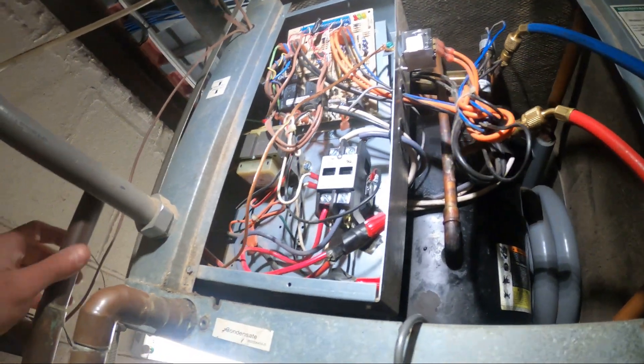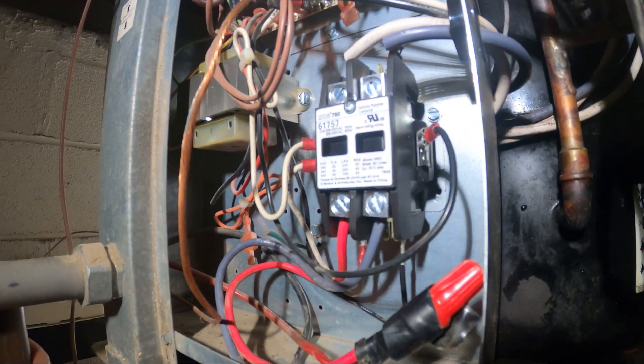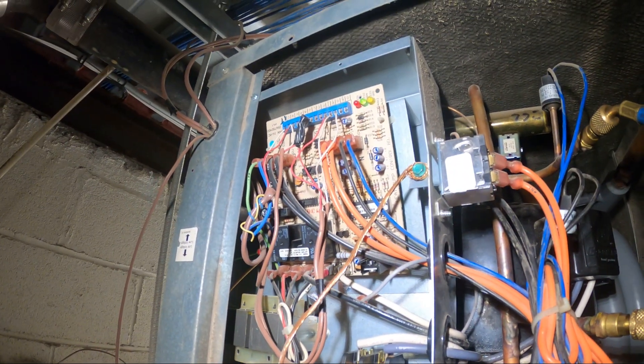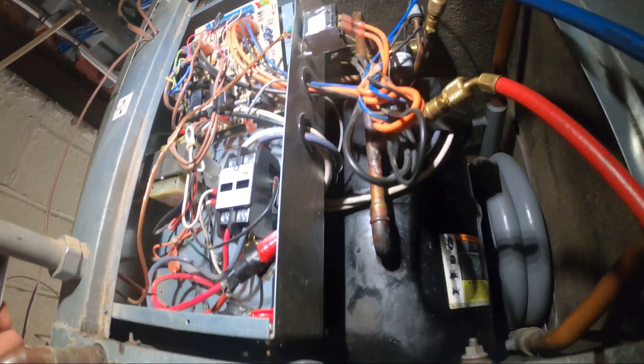I'm just going to wrap things up. Also while I was here, I replaced the contactor as the points were pitted. So if anyone found this video interesting or helpful, please drop a like, comment, and subscribe and I'll catch you all next time.